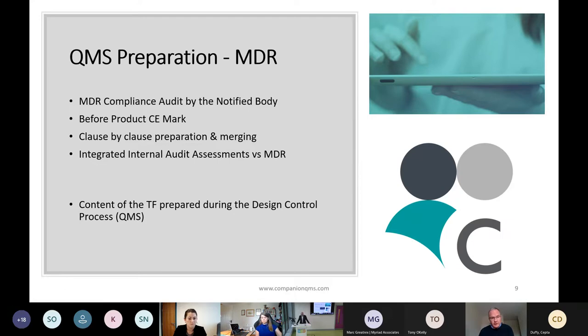All of that has to be achieved before the product is CE marked. I suppose there isn't any quick fix here to conforming with the medical device regulation. It requires several on your team to do a clause by clause preparation and merging of MDR requirements into the quality management system you're developing. Eventually you'll also need to integrate auditing of the MDR into your overall quality management system as well.